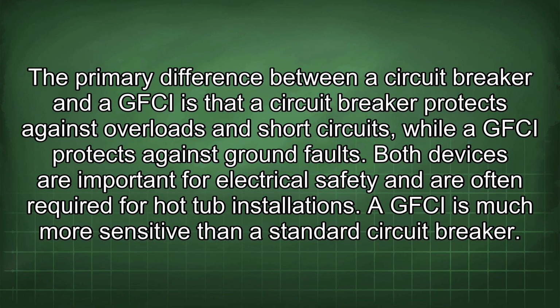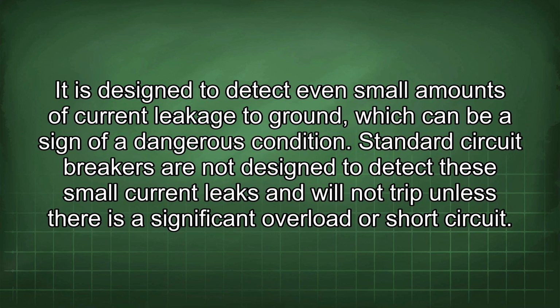Both devices are important for electrical safety and are often required for hot tub installations. A GFCI is much more sensitive than a standard circuit breaker. It is designed to detect even small amounts of current leakage to ground, which can be a sign of a dangerous condition. Standard circuit breakers are not designed to detect these small current leaks and will not trip unless there is a significant overload or short circuit.